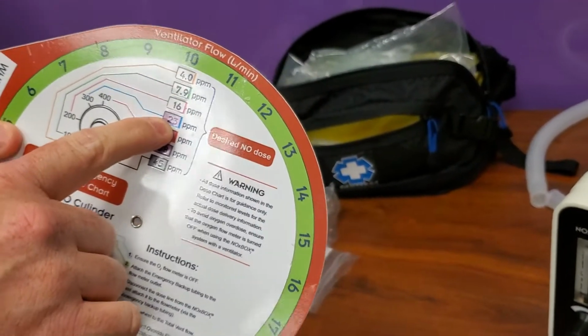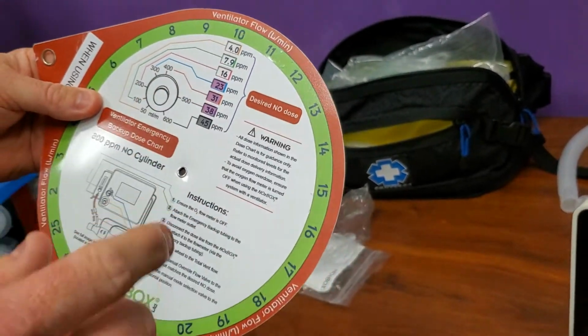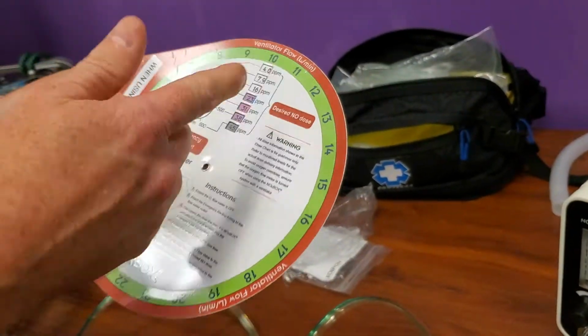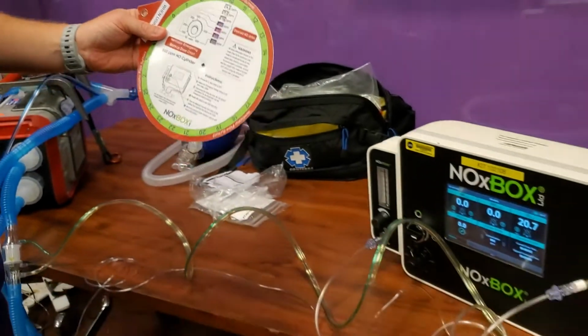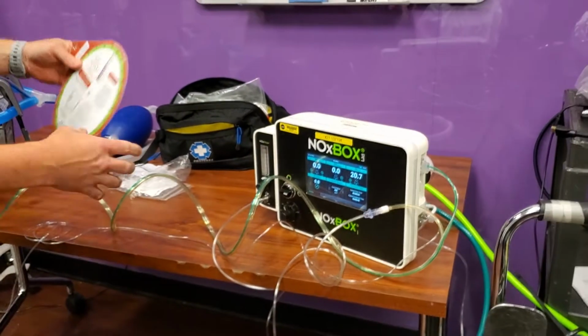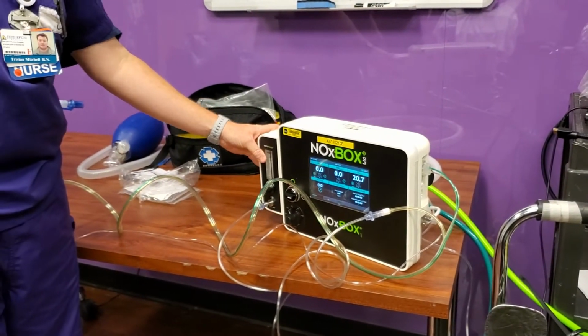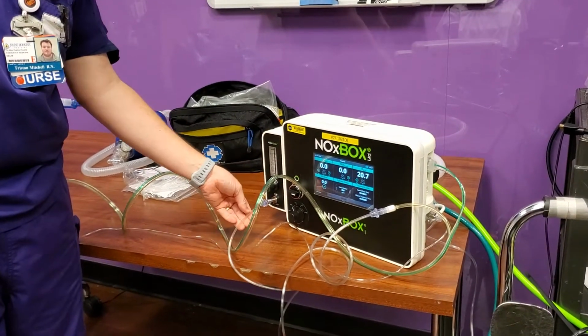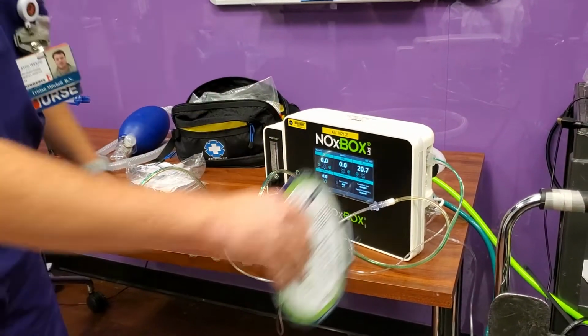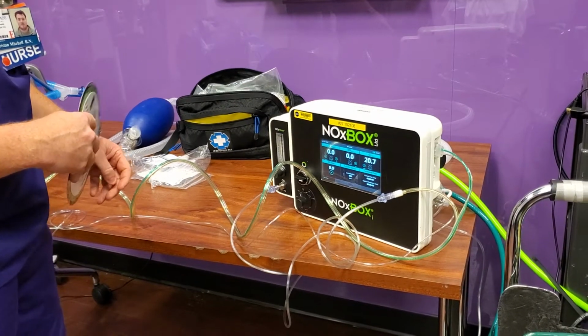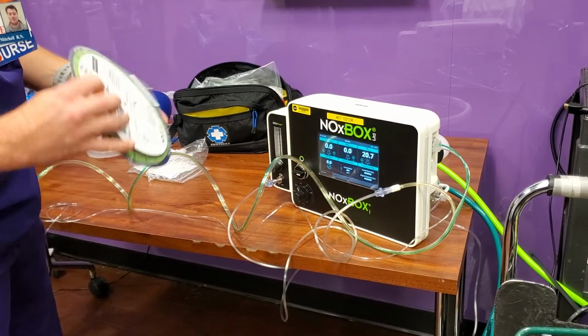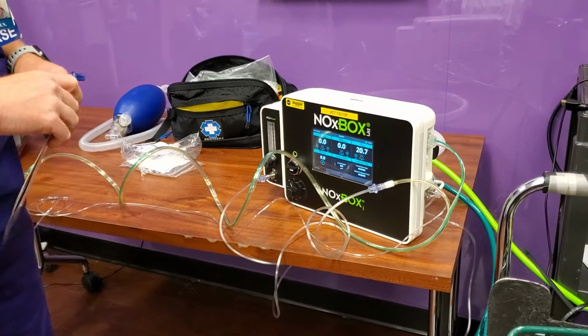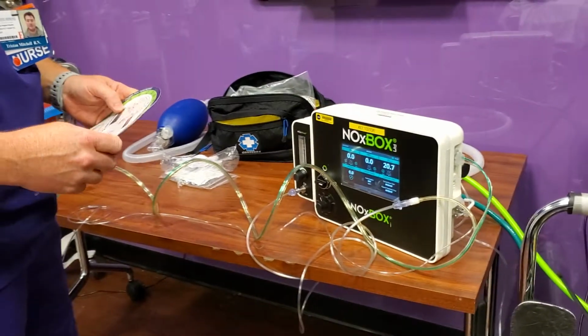Obviously, we're going to be slightly over. We'll probably be closer to about 23 parts per million, but within reason, you could go a smidge lower if you wanted to. But on the safer side, it's better to set it a little bit over to make sure they're getting enough nitric. So at this point, we do not need to turn on our flow meter. Right now, it's just naturally feeding through, going into our vent tubing, and that's going to push it through. Now, say we had an issue here and our patient went into arrest, or the ventilator completely crapped out on us.